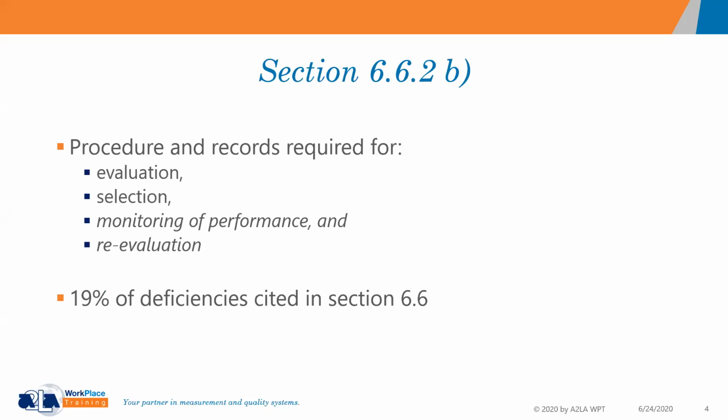As far as addressing this particular procedure, you want to have an understanding of what evaluation, selection, and monitoring are. Evaluation is just a way that you're gauging the qualifications that you set out for these particular external providers. So how are you going to measure whatever criteria you set in place against this particular provider? If you have a calibration provider, for example, maybe you want to make sure that they're accredited, so you would go and see if they're accredited. Maybe you want to make sure that they can provide calibrations for whatever is on your scope for the pieces of equipment that you're looking to get calibrated.